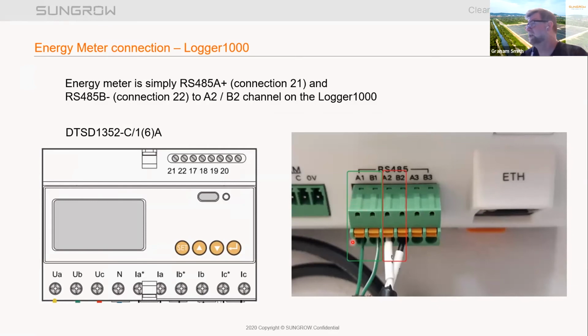And as you can see here, I've got RS485 A1B1 connected from the inverter and the A2B2 connected to the energy meter. On our energy meters, let me see, yep. You get a booklet with the energy meter, and pin 21 is the RS485A or the positive, and terminal 22 is RS485B or the negative. And you just connect those from here to here.